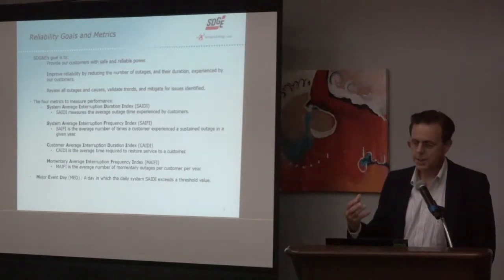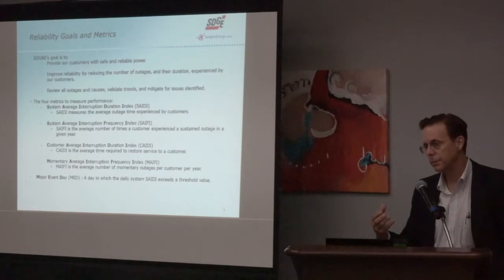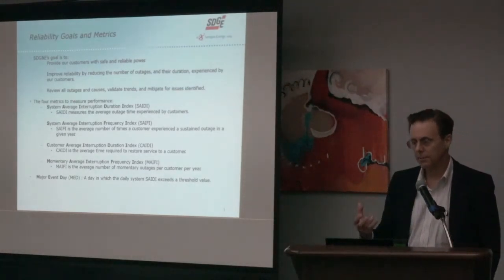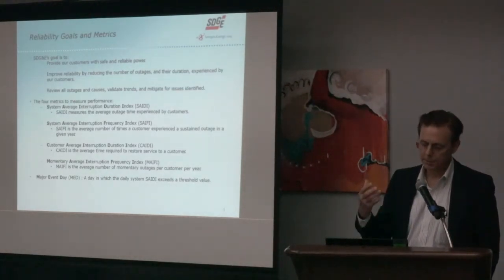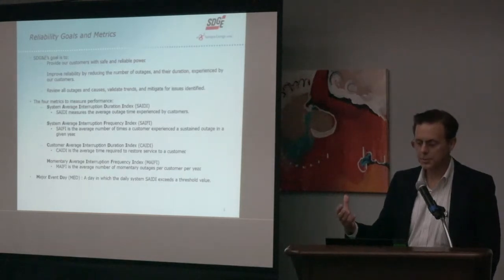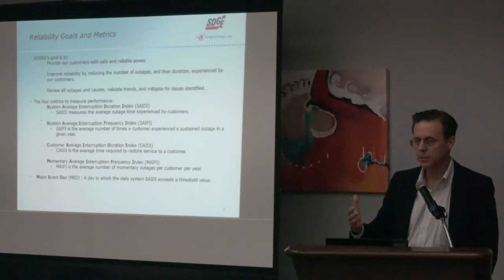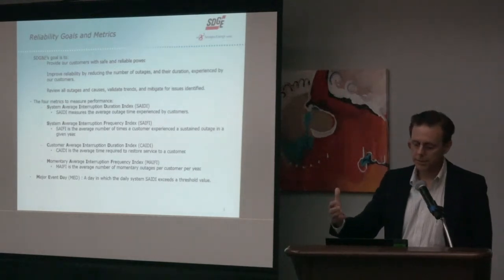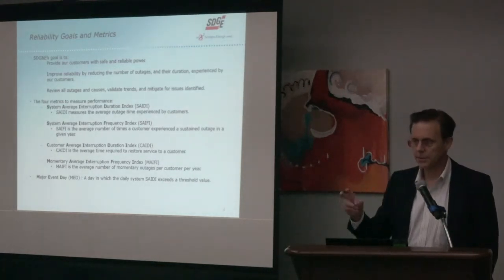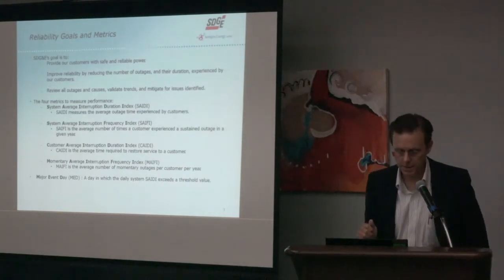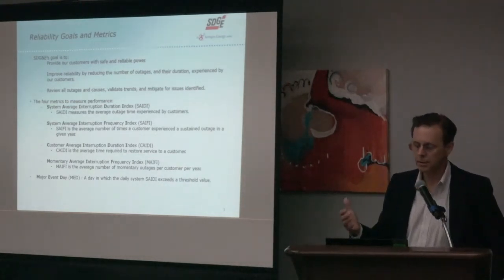We gather these measurements over the course of a year. Theoretically, we'd start at 12 a.m. on New Year's morning with a value of 0 for both. If there are no outages at that time, then when the first outage hits in the new year, we begin accumulating values for both SAIDI and SAIFI. Those are the two measurements we primarily focus on, but we actually gather information on all of these indices.